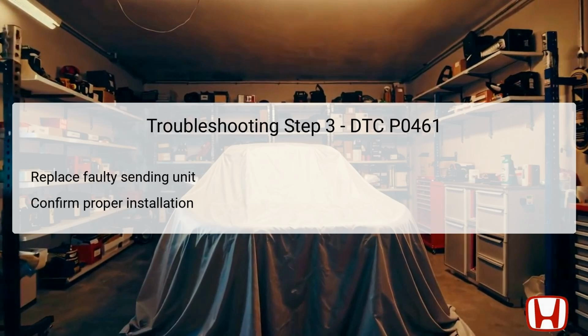After replacement, you will need to conduct a repair verification process, confirming the new unit operates as expected. This step is vital to ensure that the correct fuel data is relayed to the gauge control module once again.